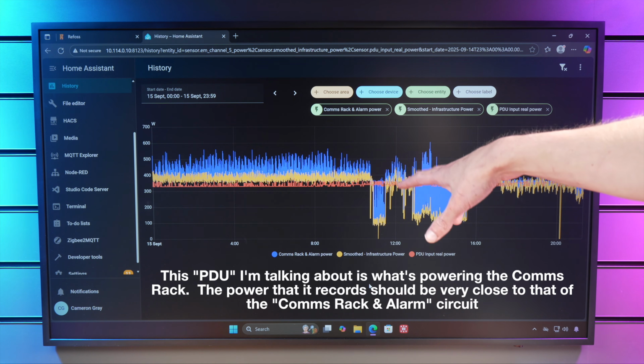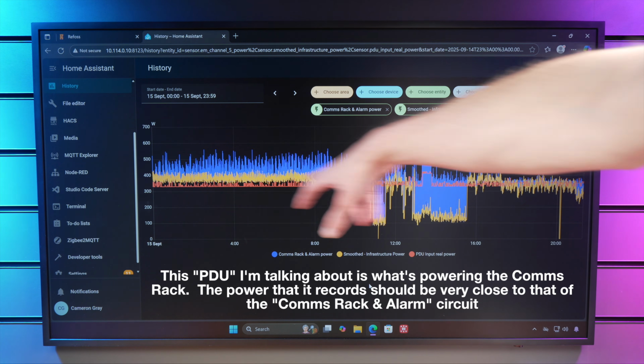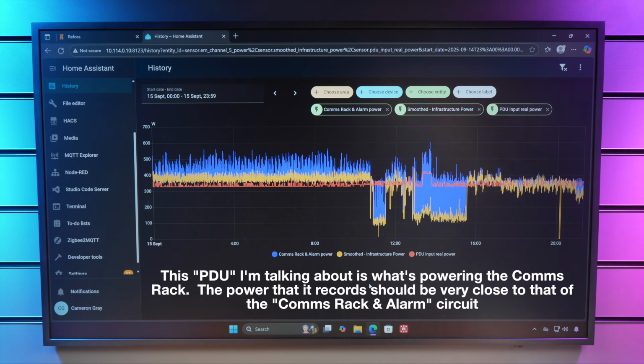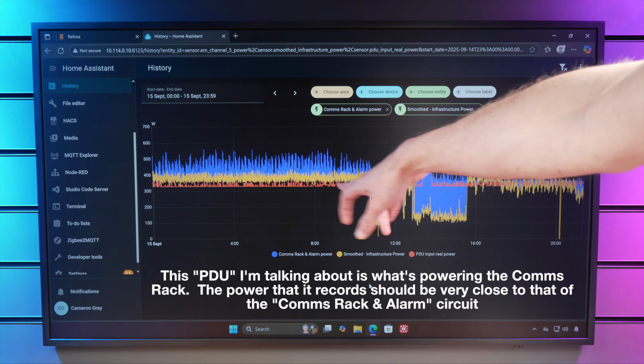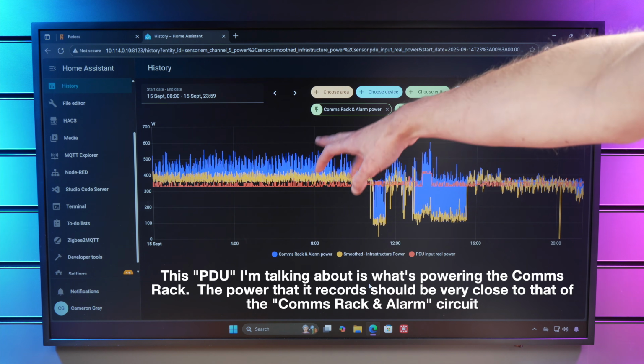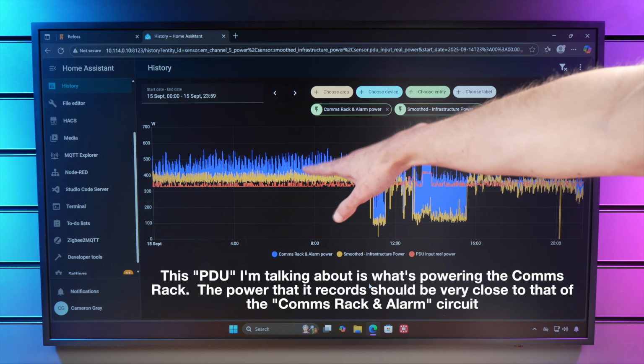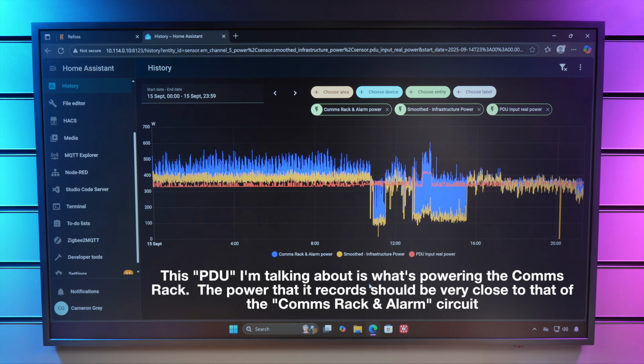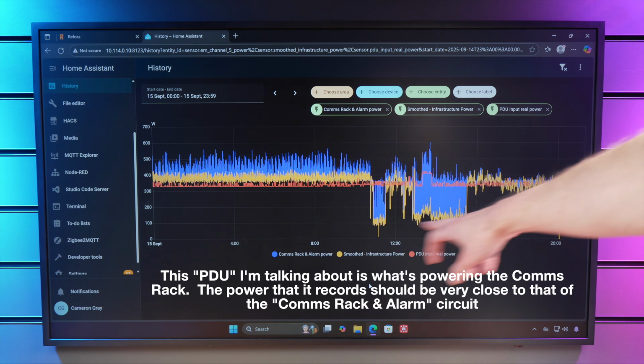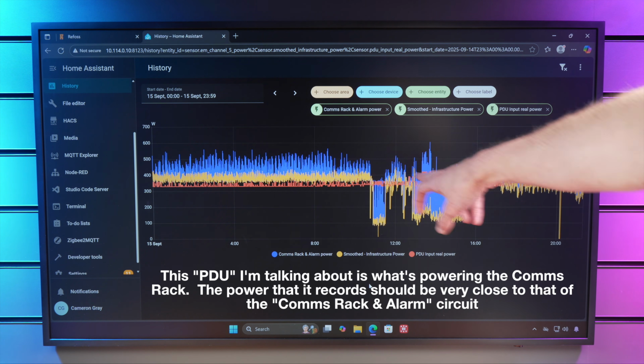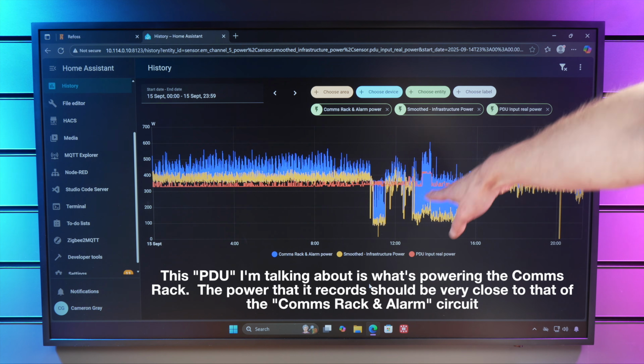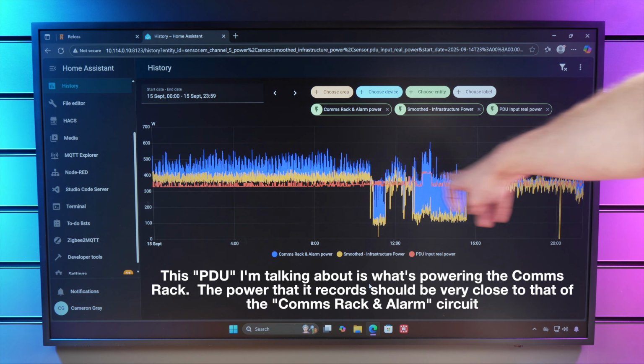Just to give a little bit more information here, what I've now added is this sort of orangey red line. That is the real power recorded by my PDU. Before here, we're tracking a little bit high above it, but not hugely. I'm not too worried about the PDU tracking a bit lower than the energy monitor, because the PDU isn't counting the UPS's consumption. But as you can see here, when that other load came on, it dropped way below that red line. So we were tracking the power as way too low compared to the actual power being recorded by the PDU.